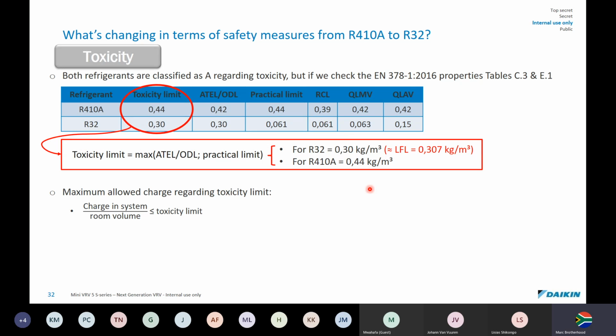So what they say is, in small little hotel rooms and that, you can't have more than 440 grams of 410A per cubic meter of air. They're a bit more relaxed with R32, 300 grams per cubic meter of air in the room. So length times breadth times height, you'll work out the volume of the room, and you can calculate all the refrigerant in the system, and if it's higher than that, it's more risky. So if there's a leak, let's say it's 0.35 here or 0.68 or whatever, there's a higher risk of somebody dying in their sleep if there's a gas leak. So we like to have 300 grams or below on the system.